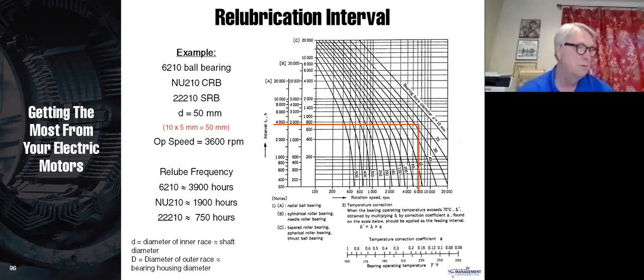Great. Do all TEFC motors have a drain plug? This is a good question. First of all, you can have a TEFC motor with a sealed bearing. If it has a sealed bearing, no, it's not going to have a drain plug because you can't re-grease it. So there are a lot of TEFC motors that have non-regreasable bearings. I've also seen some motors, and people will say, look at this motor, it's got this Zerk fitting, but there's no drain plug. And I kind of scratch my head at some of those things. And so in some cases, you may have to go back and check with the manufacturer and find out what's going on there. Because if you have a Zerk fitting to put grease into the motor, you have to have a drain plug. Otherwise, where's that grease going to go? But it can be an issue.